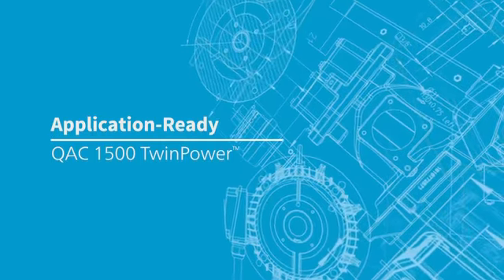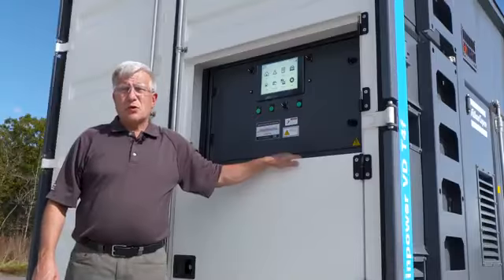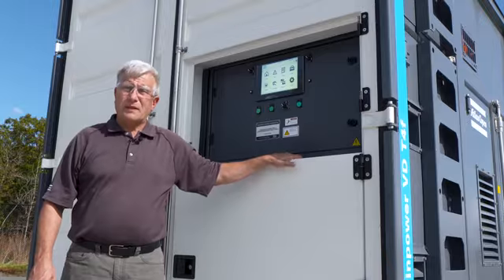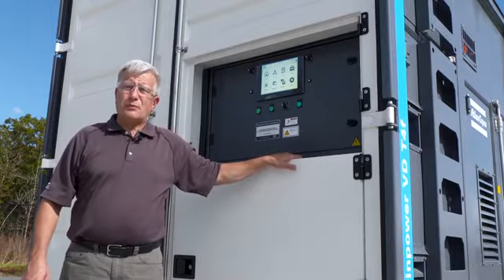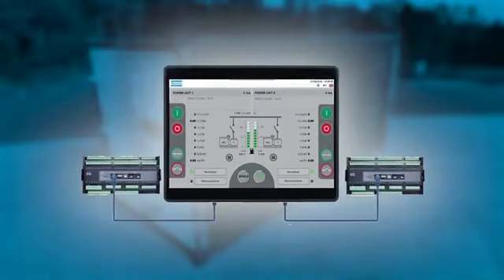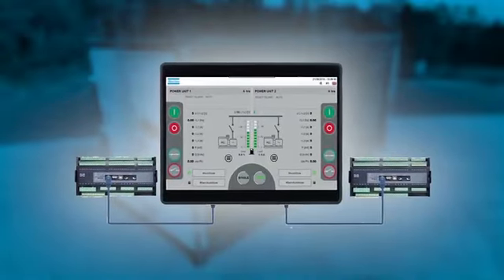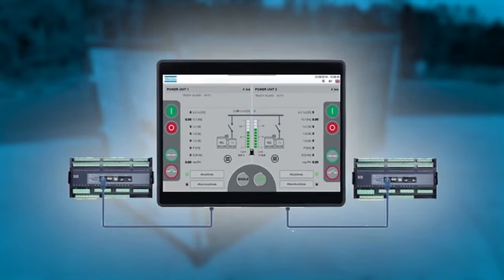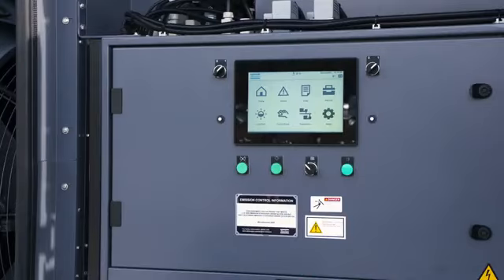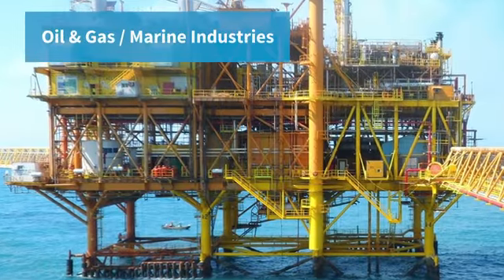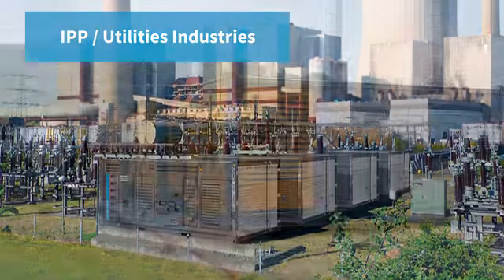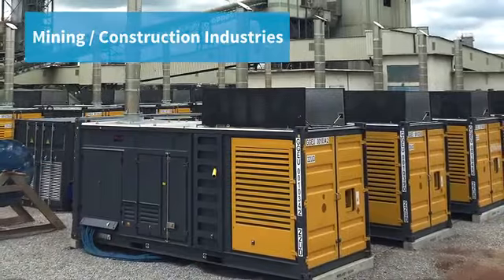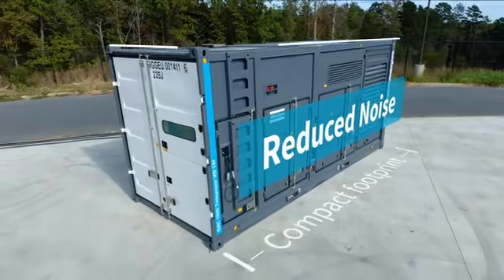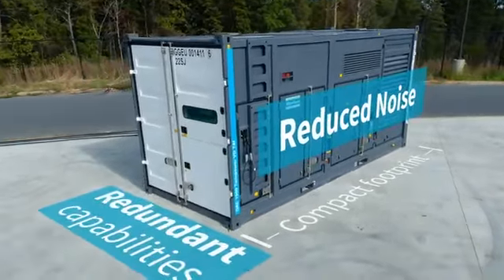Application ready. The centralized QC4004 paralleling controller takes control of the application and allows two generators to operate as one as needed. The two generators combined with the controller give you redundancy so you never lose power. The TwinPower controller can be set up to cover nearly any power application in the rental business, including peak shaving, blackout-free critical standby, transformer maintenance, export power, and even more. Reduced noise levels, compact footprint, and redundant capabilities make it perfect for applications such as events.